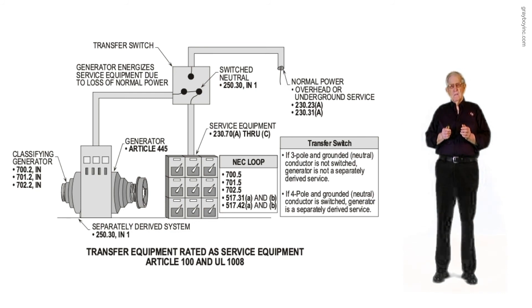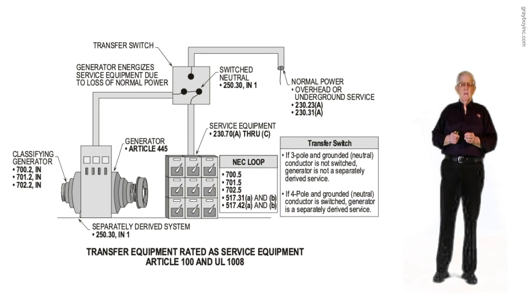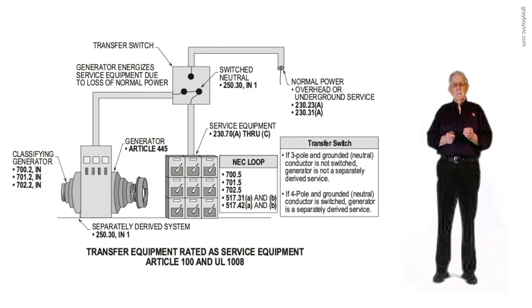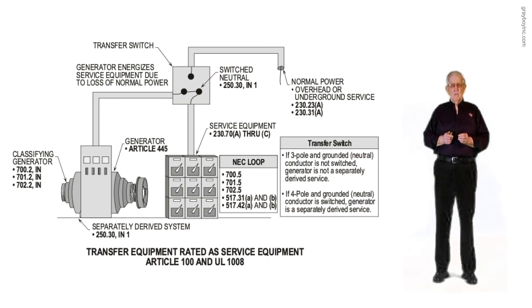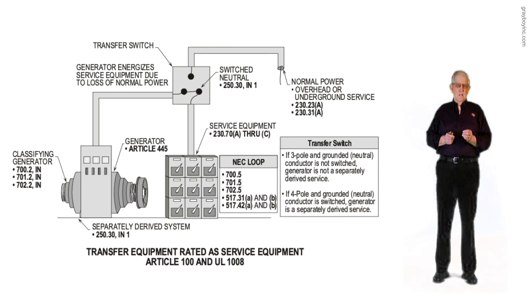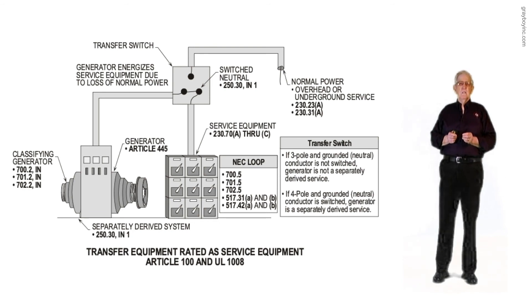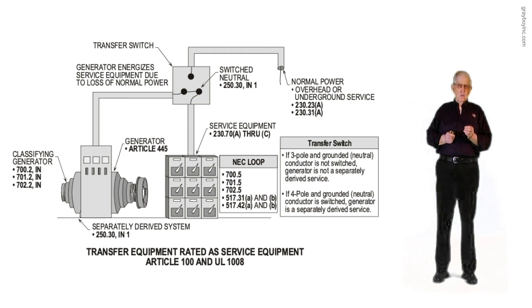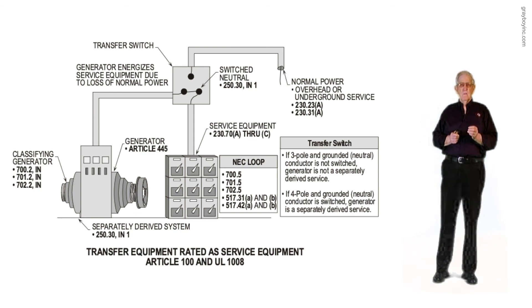This illustration basically illustrates how to classify a generator and the transfer equipment — is it rated as service equipment or not? Is it a three-pole transfer switch or a four-pole transfer switch? UL 1008 goes into more depth about the transfer switch — whether it's used as service equipment and how it would have to be rated. You could also go to UL.org and call up the UL White Book for General Industrial to read about these transfer switches in the electronic version.